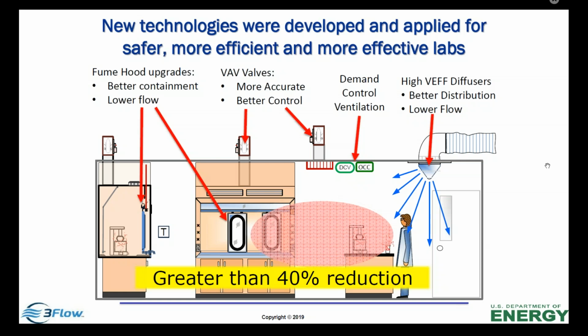The one on the right, which says High VEFF diffusers, I'm not going to get into that, but this is very exciting. We've been doing a lot of studies with UCI because we've been working there with their Smart Lab system for over a decade. And one of the things they asked us was, hey, is 6 air changes in one lab the same as 6 air changes in another? And we said, oh, well, let's do a study. And what that boiled down to is we found that if you start putting more air into a room, the air changes going up may not be the best thing for that space. VEFF, or ventilation effectiveness, is how well air sweeps from supply to exhaust through the space itself. And the better it sweeps through the space, a lower air change rate with a good VEFF rating could be more efficient and safer than a higher air change rate.